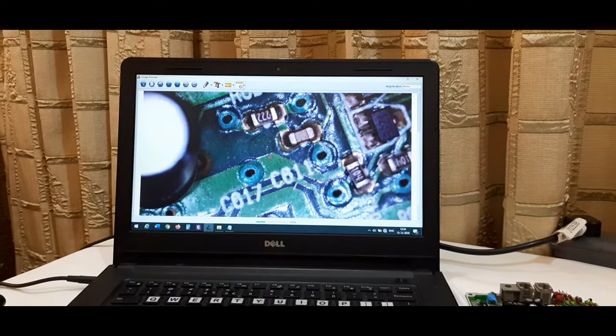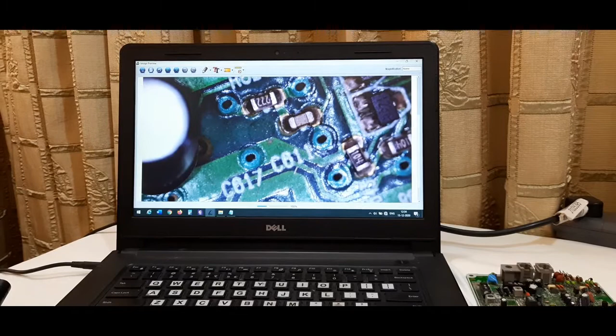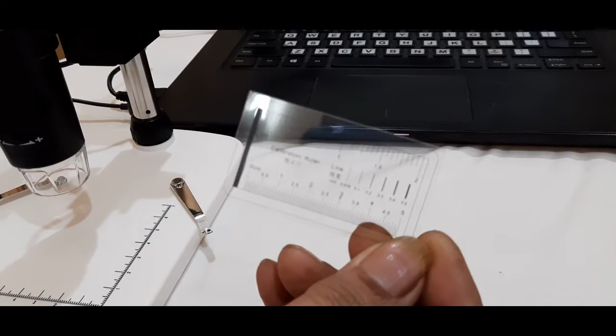So there is another feature of calibration present in this microscope. To use this feature, we need to capture a new image and then we will proceed further. Now we have supplied one calibration scale along with this microscope. So let's use this scale. See, the line of this scale should be in parallel to the coordinates displayed on the screen. So align the calibration scale so that it perfectly fits in the coordinates, and it should be parallel to this line which is marked on the calibration scale.